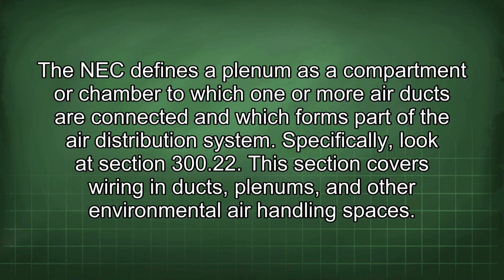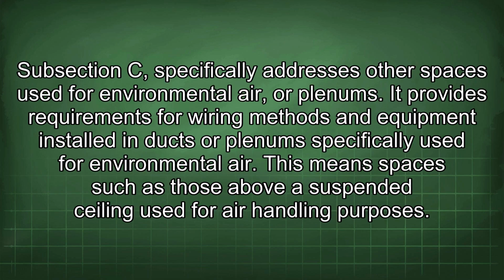Specifically, look at section 300.22. This section covers wiring in ducts, plenums, and other environmental air handling spaces. Subsection C specifically addresses other spaces used for environmental air, or plenums. It provides requirements for wiring methods and equipment installed in ducts or plenums specifically used for environmental air. This means spaces such as those above a suspended ceiling used for air handling purposes.